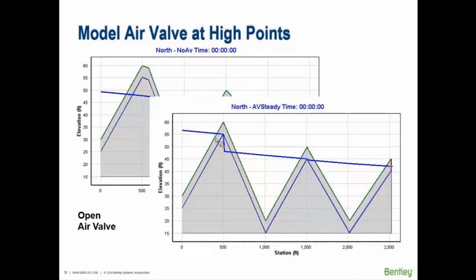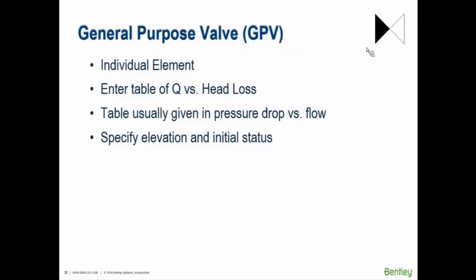Previous versions of WaterCAD assumed a siphon occurs at high points, which is rarely the case. Now you can truly model an air release valve and correct the flows, heads, and locations where flow transitions from full pipe pressure flow. For any other valve purpose, use a general purpose valve — providing a flow versus head loss curve — and apply it in the model.